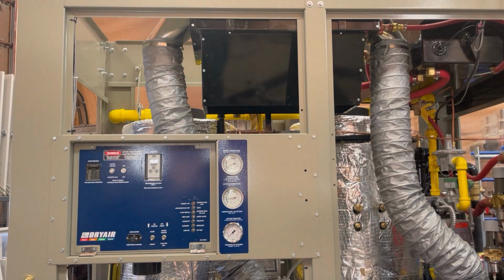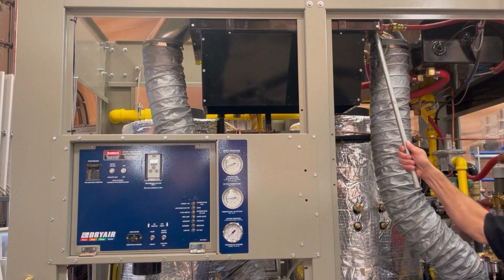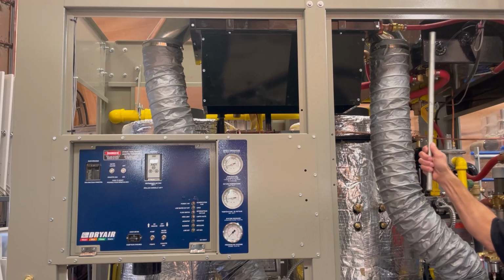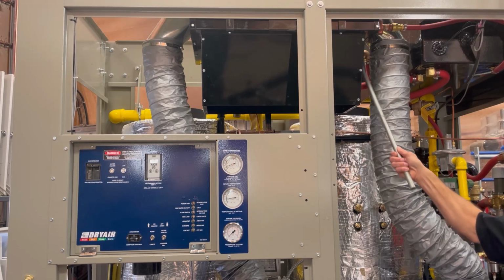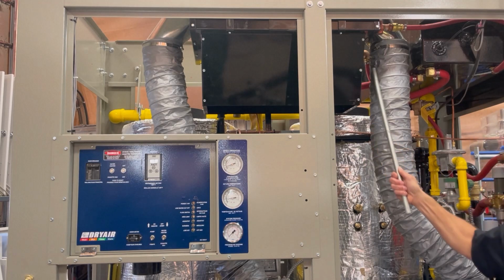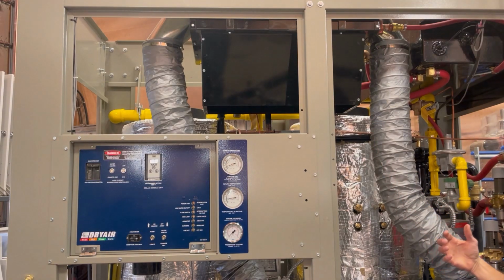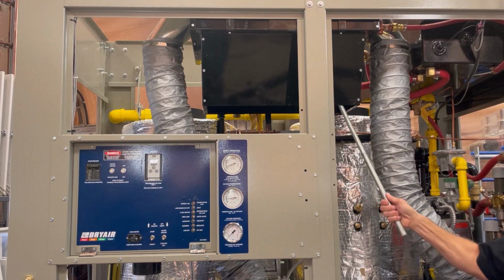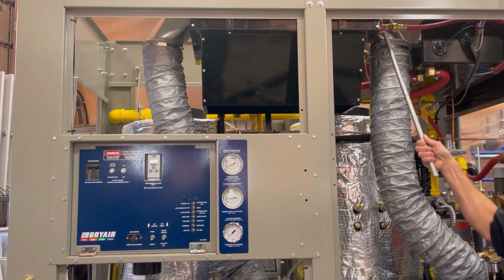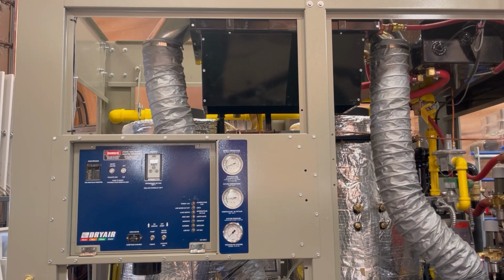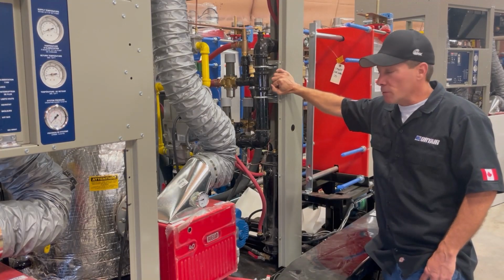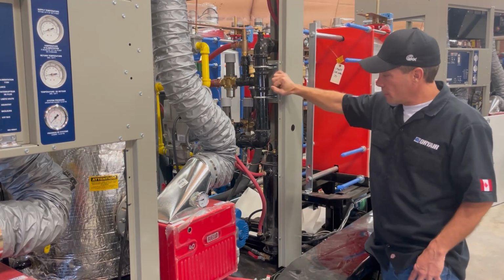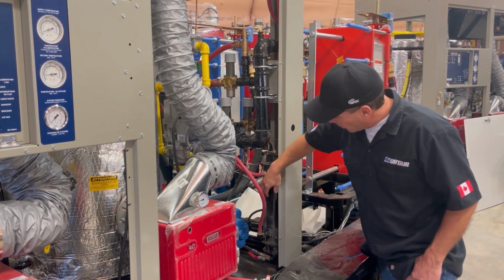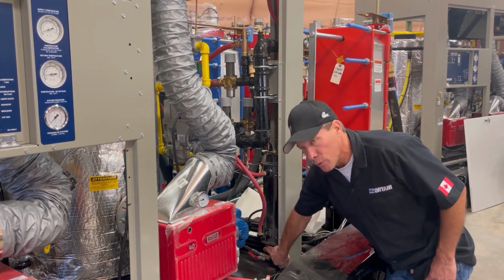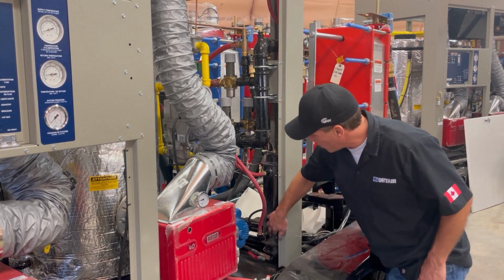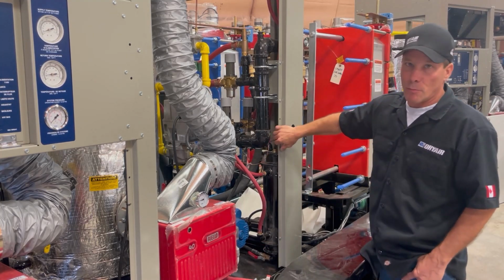For our preheated air, we have a radiator at the top of the unit above your burners. We have hot glycol that comes through the radiator on this side, returns out on the back side. As the burner kicks on, your fan will suck air into the burner, which then pulls air up through this chute, across your radiator, through this gray sleeve into your burners. So we have 70-degree fuel running through this machine at all times. And how we do that is through this tube. Hot glycol is on the outer tube, warm fuel is on the inside. Your fuel comes up across this tube and over into your burner.